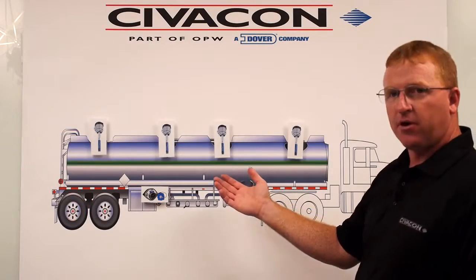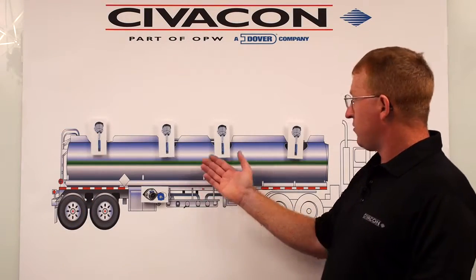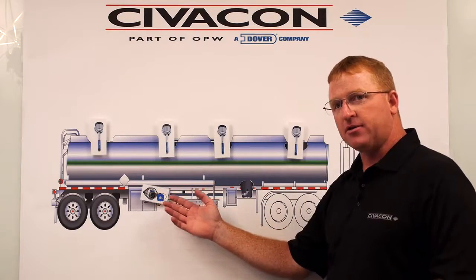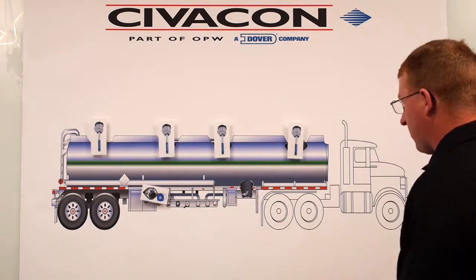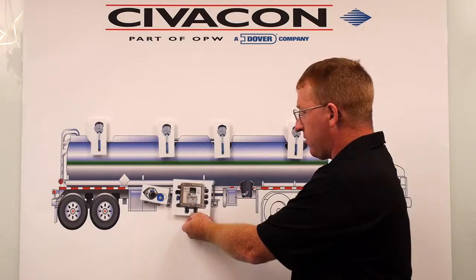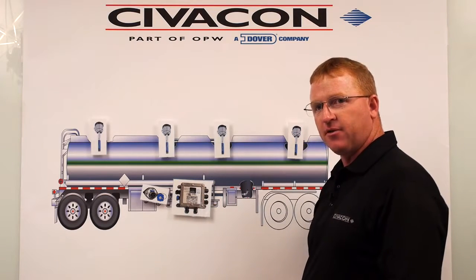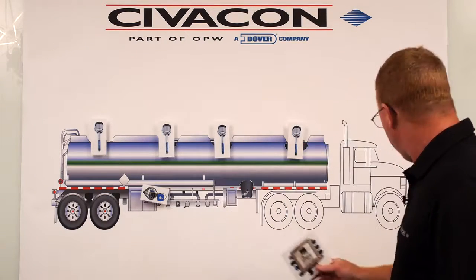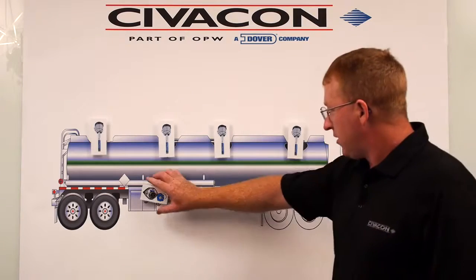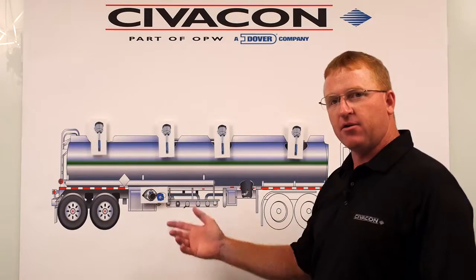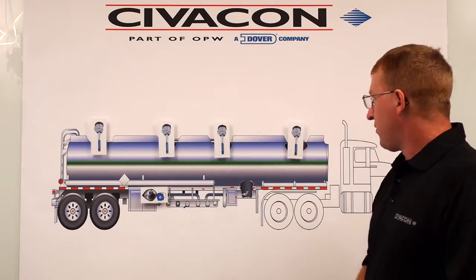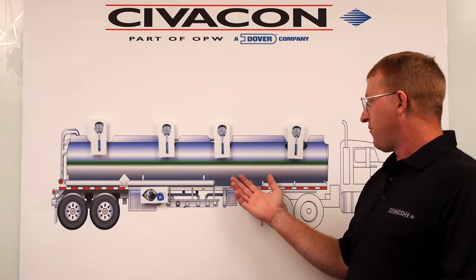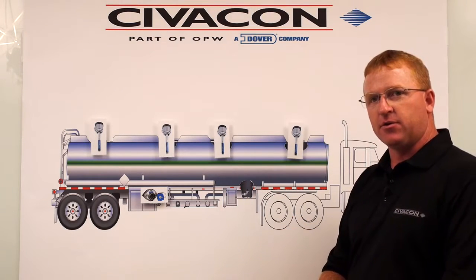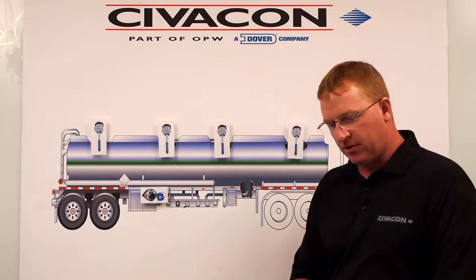Notice on the system we're working with here, the 5-wire system, there's no onboard monitor like in the 2-wire. On a 2-wire, you typically have an onboard monitor that helps you troubleshoot the system and the faults with it. On the typical 5-wire, like we're dealing with now, it only has a blue socket, or the optic socket. The only way to effectively troubleshoot this is with some sort of tester, like the one we showed previously in the film.